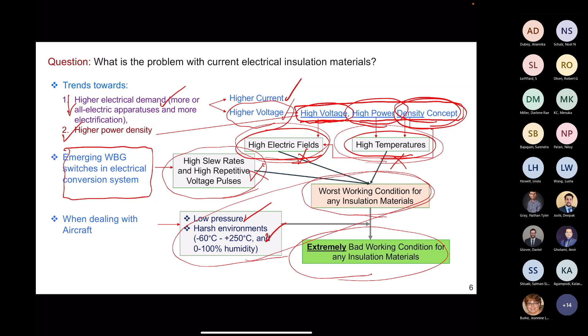We can divide insulation degradation into four factors: space charge, intrinsic aging, treeing, and partial discharge. Partial discharge, or PD, has the most effect on degradation of solid dielectrics, and it's inevitable because we cannot have dielectrics without defects, voids, and cavities. There is no such thing as a solid dielectric without them. That's why PDs are very important.